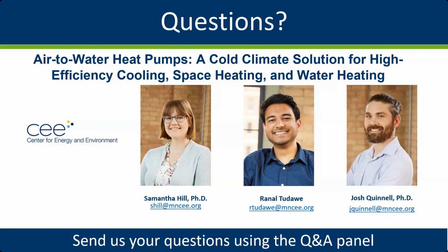So it remains an open question about how effective air-to-water systems will be with emitters that are designed for higher temperatures. I will say that I'm still quite optimistic about the potential, because one thing we should also recognize is most of these high temperature emitters were designed for buildings that were built a long time ago. So even if we expect a lot less emitter capacity from those systems at these low supply temperatures, those buildings are very likely to have had significant upgrades that will have reduced their building loads. Things like weatherization and new windows may reduce the load on these buildings enough such that we could actually get adequate capacity for the building's needs at those temperatures.